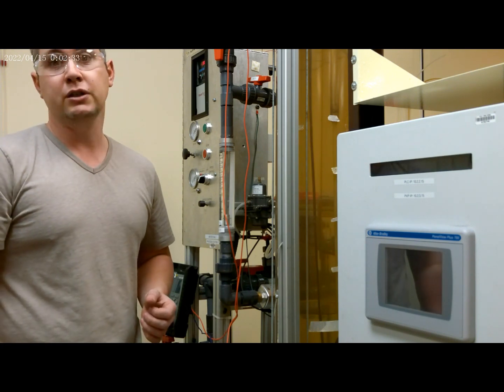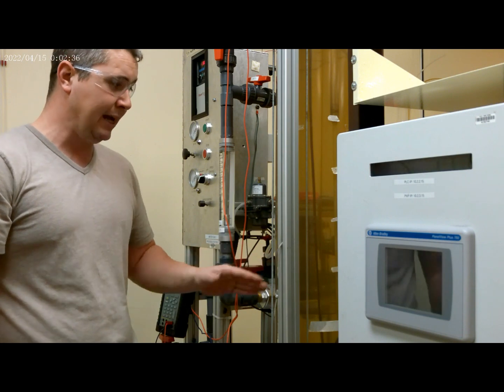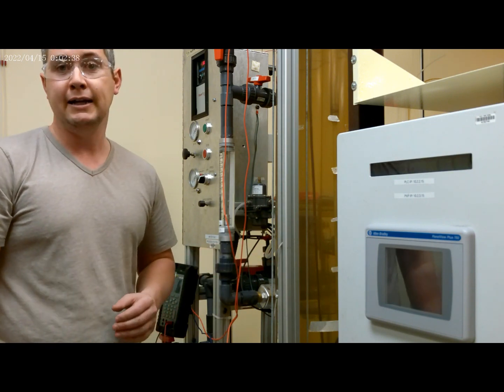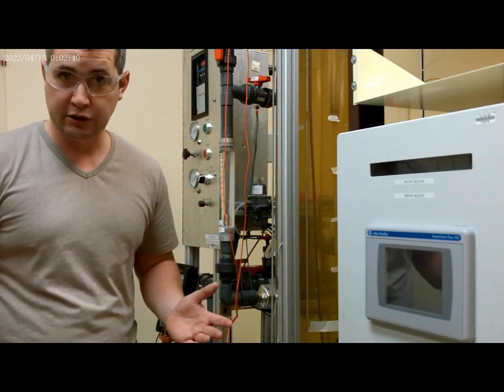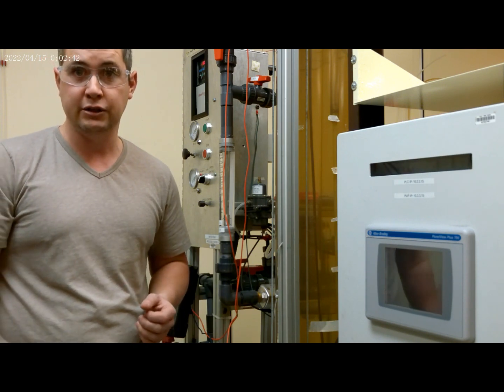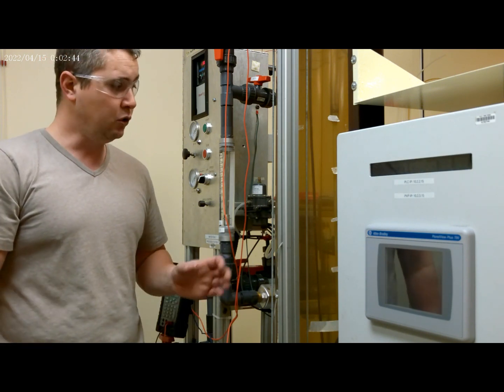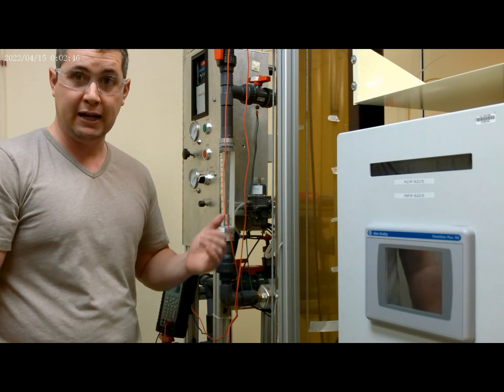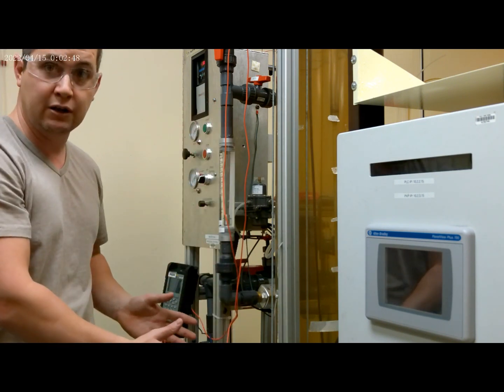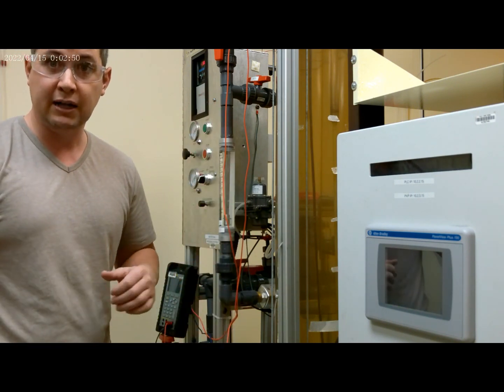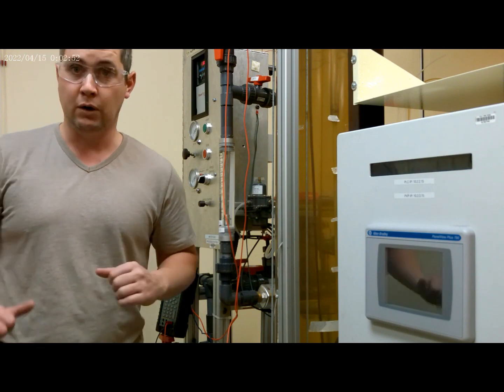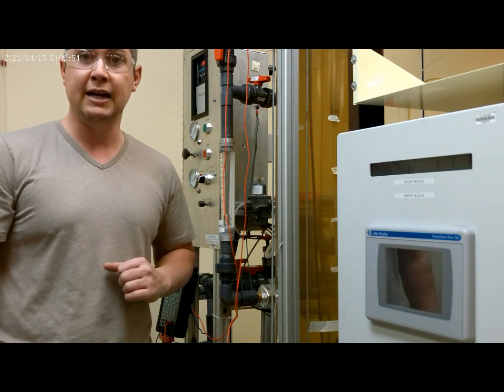One of the downsides to the capacitance probe is that water splashes onto it, and that changes the dielectric material, which changes the reading. So it doesn't like water splashing, and in this system, water does splash. Sometimes you have to wait for a while and let the water level steady out.